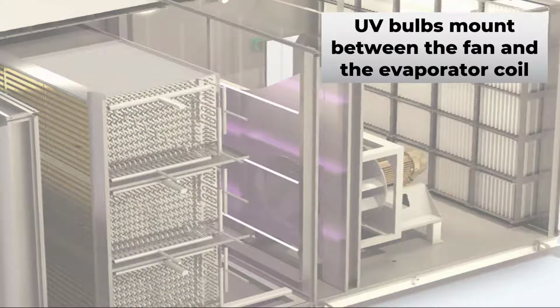Here's a model of the interior of an AcuAir unit. The UV bulbs mount between the fan and the evaporator. The standard Frick AcuAir design allows for enough room, about 40 inches, to be able to properly position the bulbs.